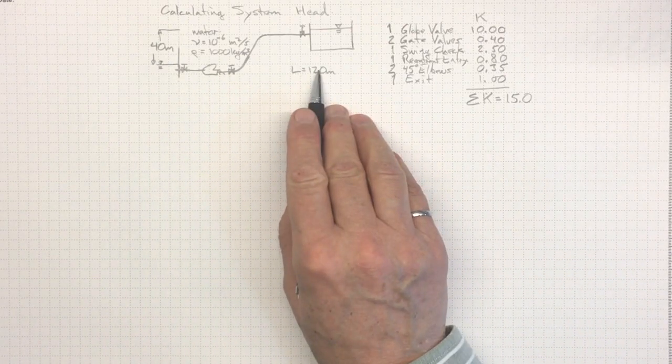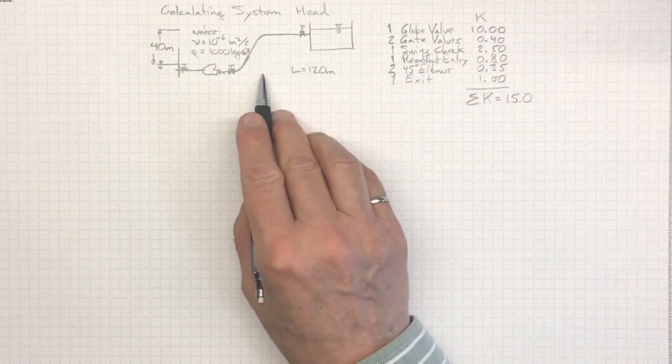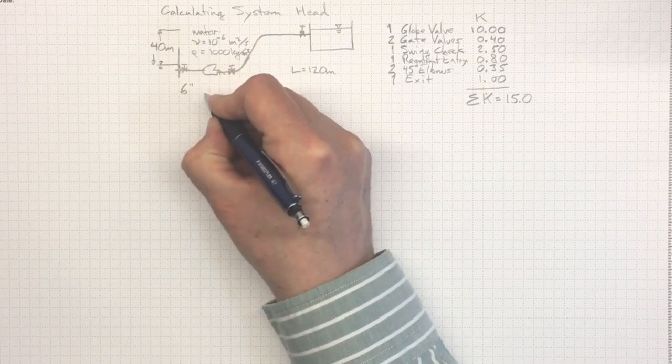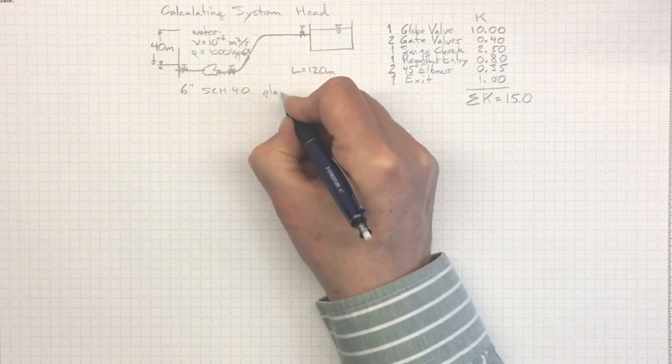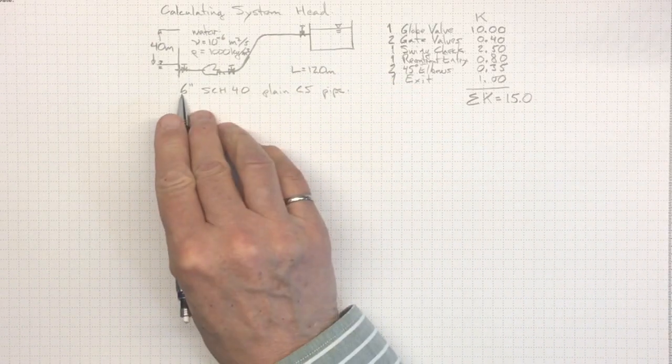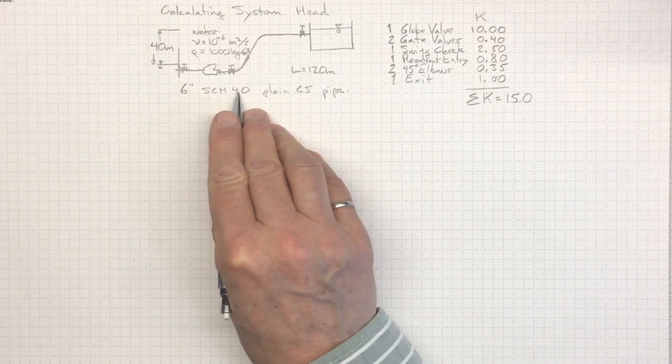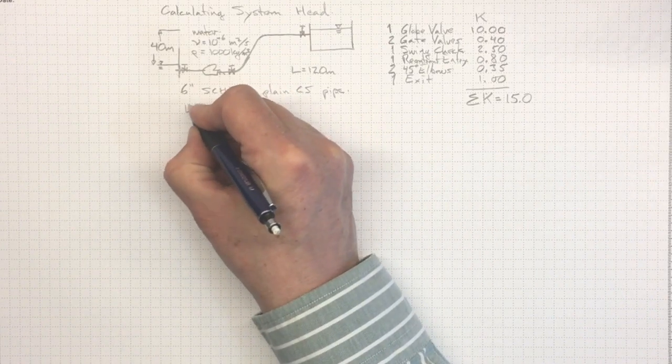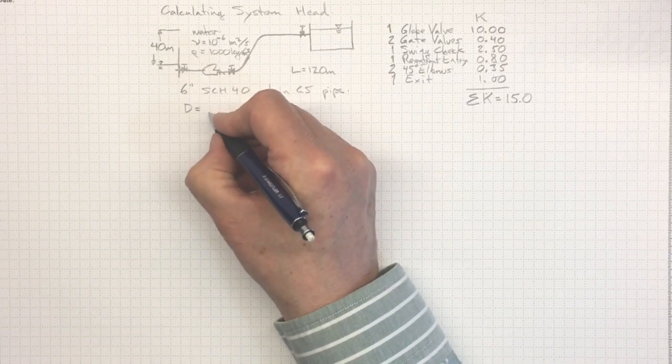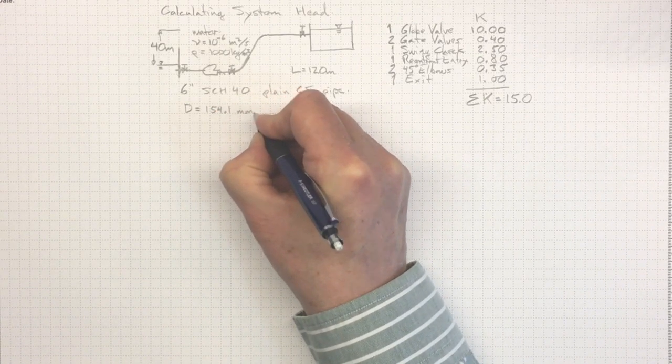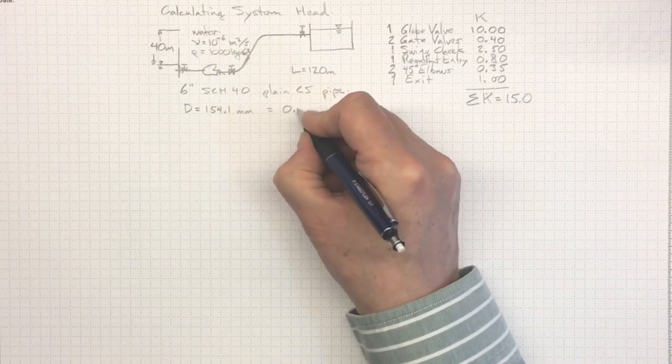So, we know how long this pipe is. We know what the K factors are. We need to know how big a pipe it is. Well, let's say it's a medium-sized pipe. It's a 6-inch Schedule 40 plain carbon steel pipe. Now, to know what that inside diameter actually is, we'll have to look it up in a table for Schedule 40 pipe. And I looked it up, and I found out that the inside diameter of a Schedule 40 pipe is 154.1 millimeters. Or, being careful to keep everything in consistent units, 0.1541 meters.